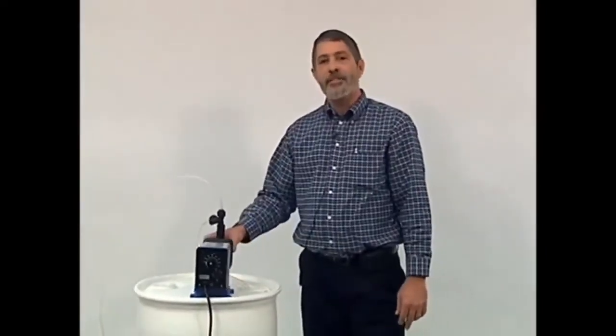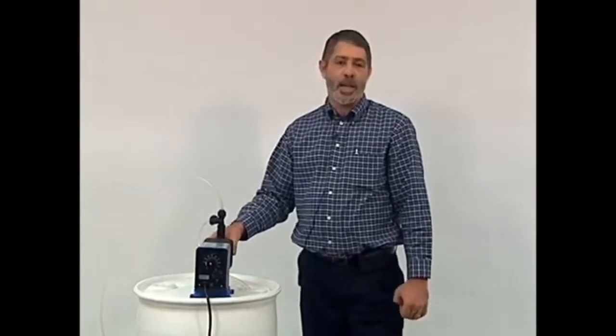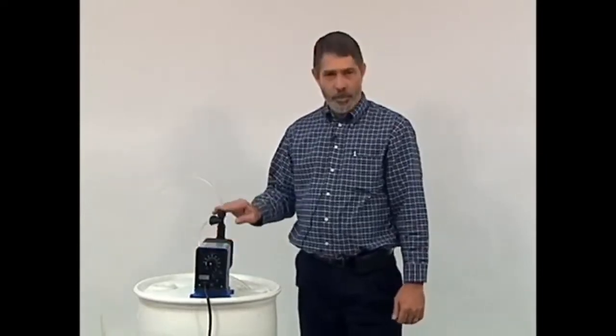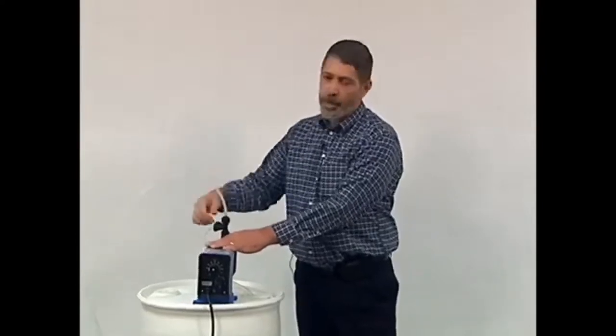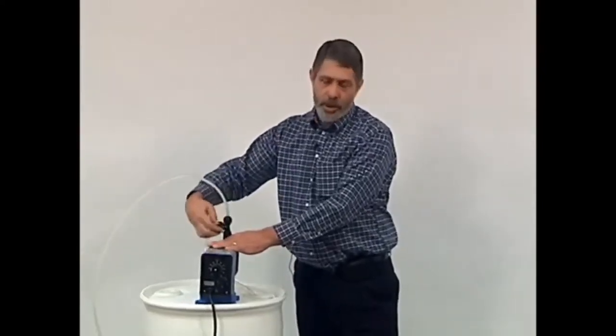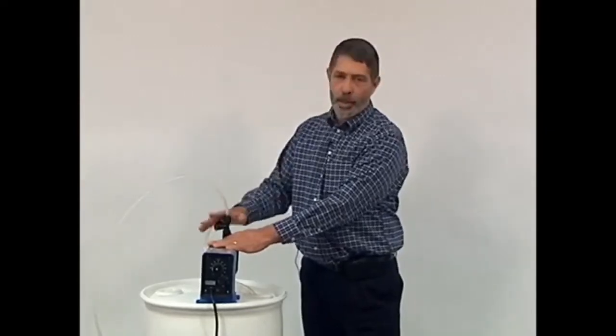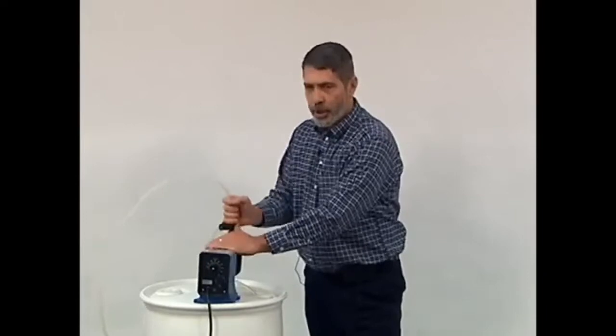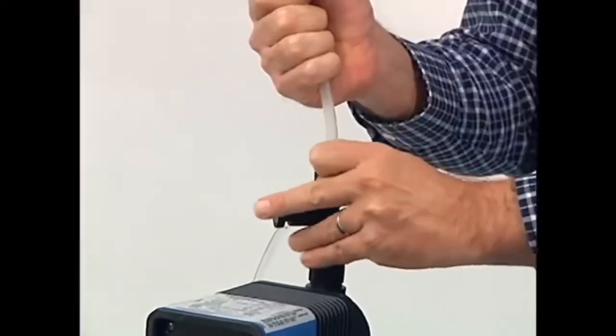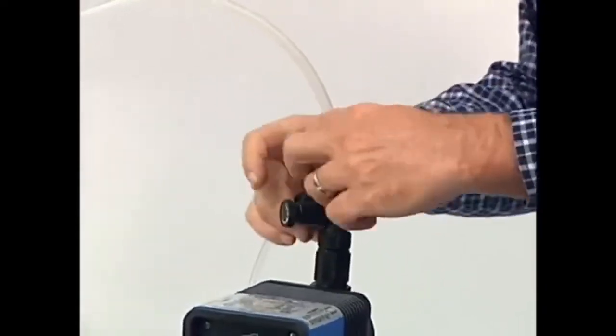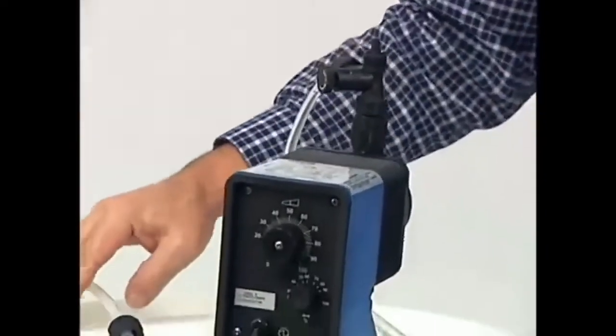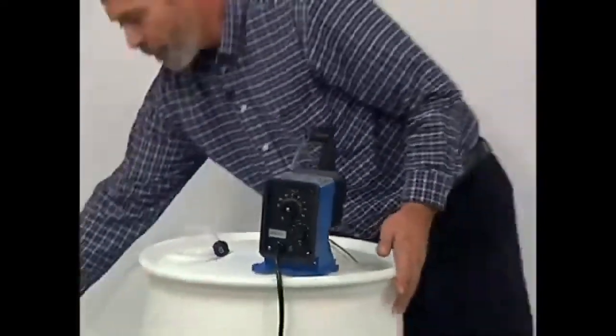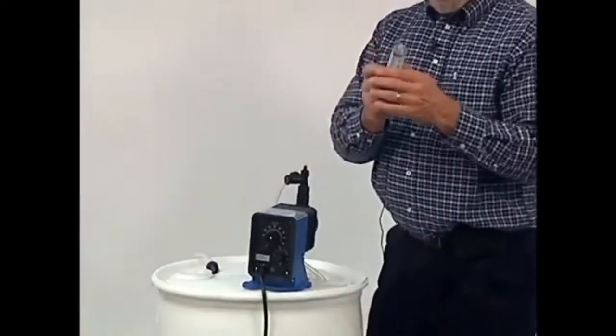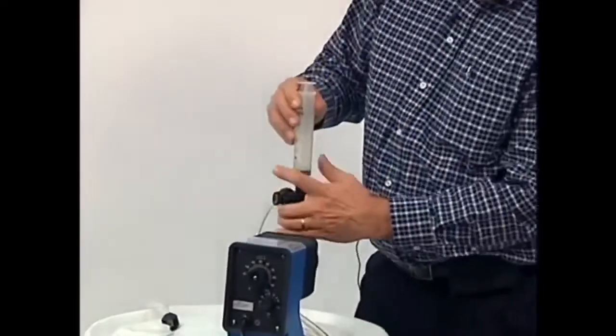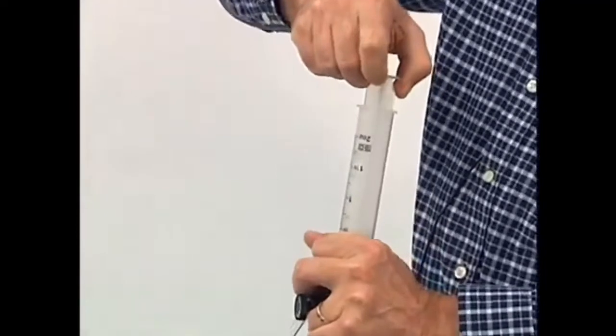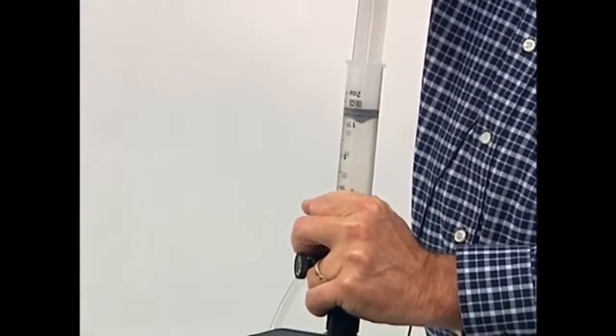If all else fails, we can use our Gelman syringe to pull a vacuum through the top port of your pump here before you ever remove this discharge tubing. Open your priming valve to relieve all pressure on the system, and then you can take this top nut off so that you can get to the top section of the pump. Once you have this exposed, it may be possible for you to use this to pull a vacuum, which will help your pump to prime.